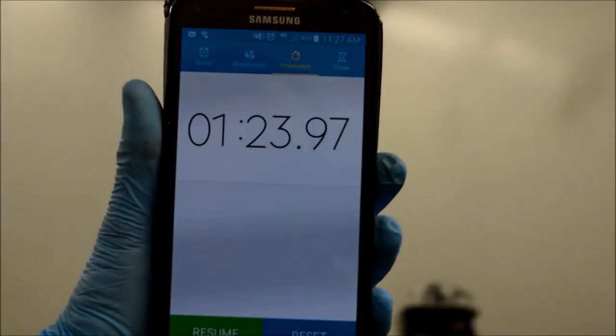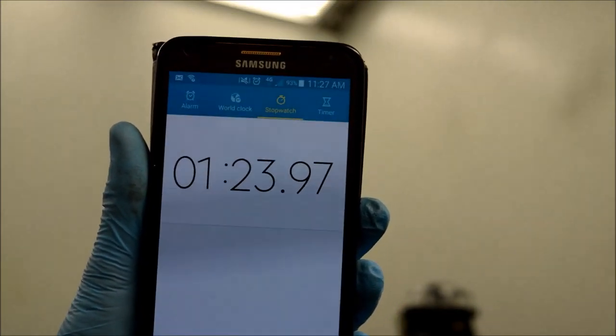You might not be able to see it on camera, but you can still see some smoke. And we're probably about there. So if we look at the time, as you can see there on the timer, it's actually made it at 1 minute 23 seconds. So what we're going to do now is log this down on our piece of paper and we'll keep a log of the spray booth test clearance times, and then obviously we'll do another one next time we come to service the booth.